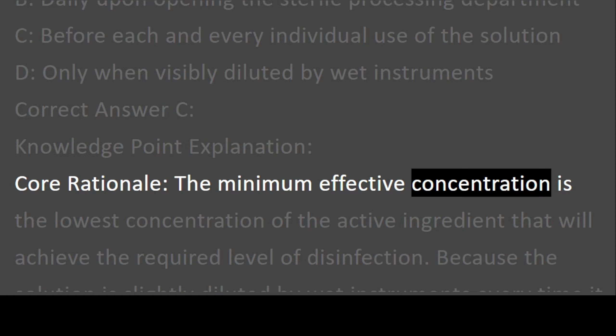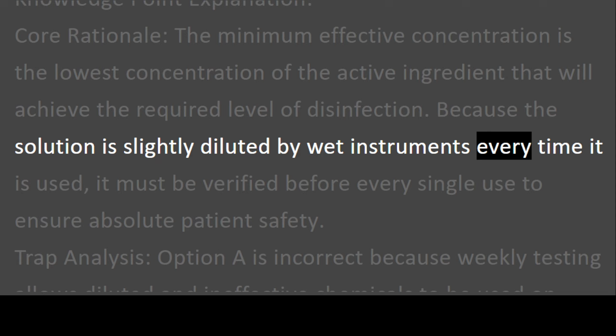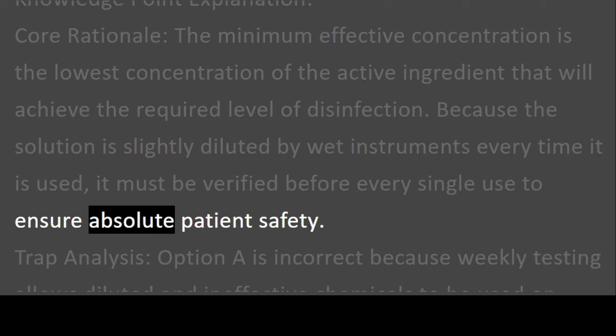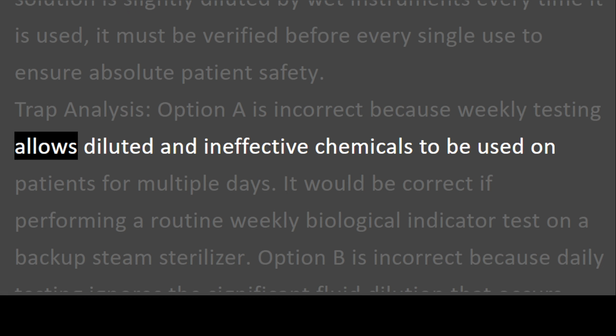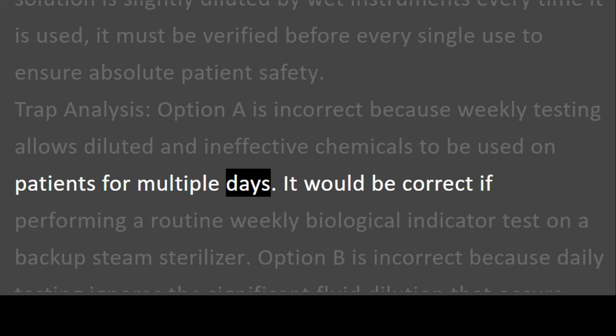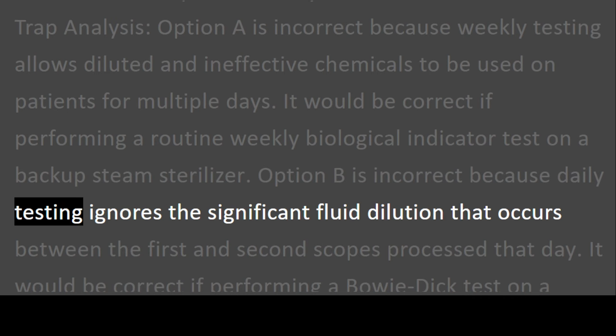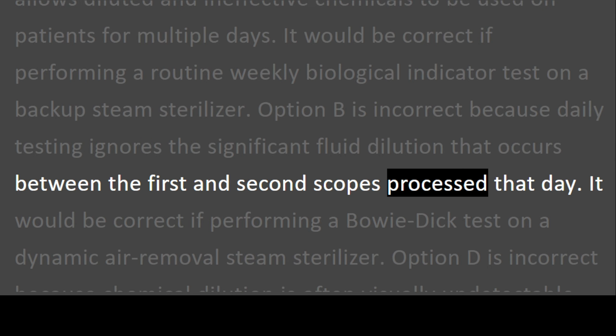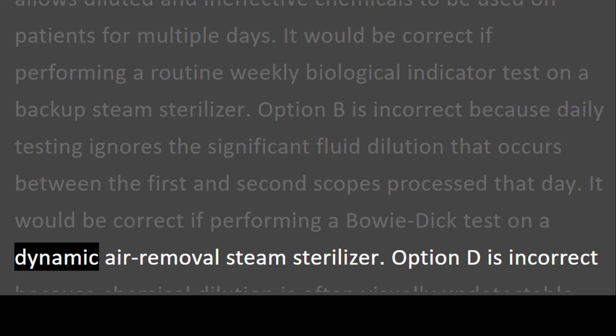Core rationale: the minimum effective concentration is the lowest concentration of the active ingredient that will achieve the required level of disinfection. Because the solution is slightly diluted by wet instruments every time it is used, it must be verified before every single use to ensure absolute patient safety. Trap analysis: option A is incorrect because weekly testing allows diluted and ineffective chemicals to be used on patients for multiple days. It would be correct if performing a routine weekly biological indicator test on a backup steam sterilizer. Option B is incorrect because daily testing ignores the significant fluid dilution that occurs between the first and second scopes processed that day. It would be correct if performing a Bowie-Dick test on a dynamic air removal steam sterilizer.